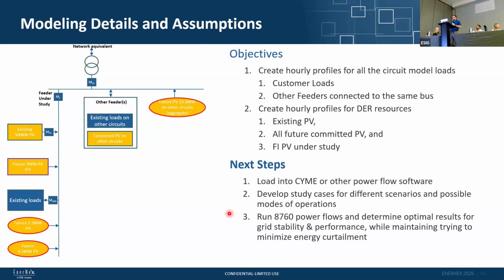And so loaded into CYME, but then we needed to look at developing some study cases. So different scenarios that are possible, different modes of operation in terms of control modes for the FI to provide volt var support or volt watt support if it was necessary, and seeing which one of these study cases provides the best results to maintain performance while also minimizing energy curtailment.